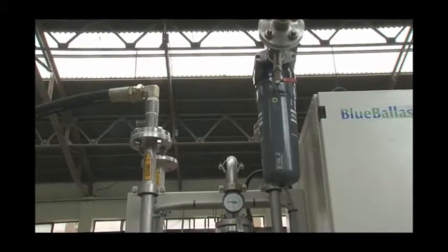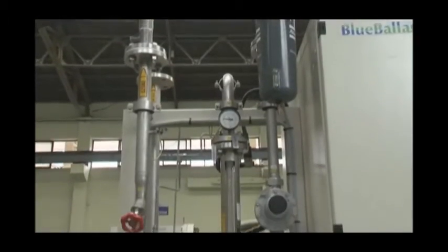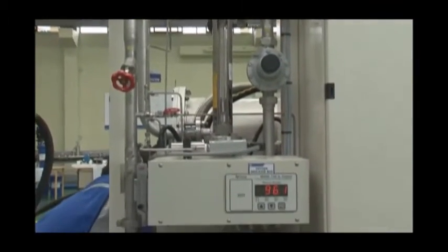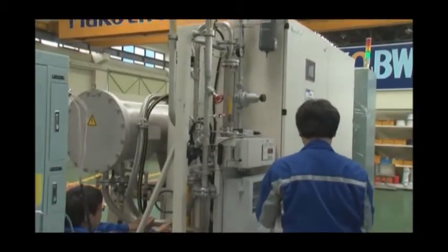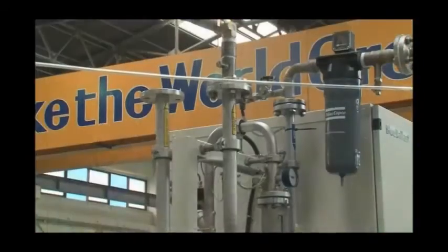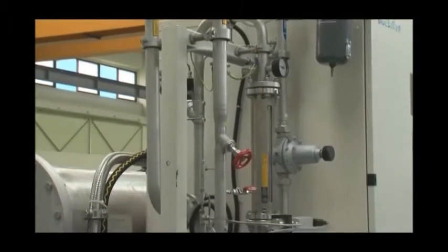The oxygen dew point is monitored before ozone generation. In case oxygen dew point is higher than minus 65 degrees Celsius, the air quality to oxygen generator and the purity of oxygen need to be checked.